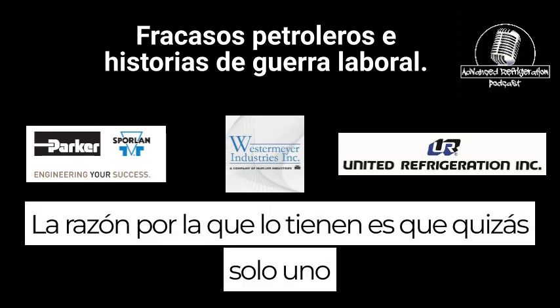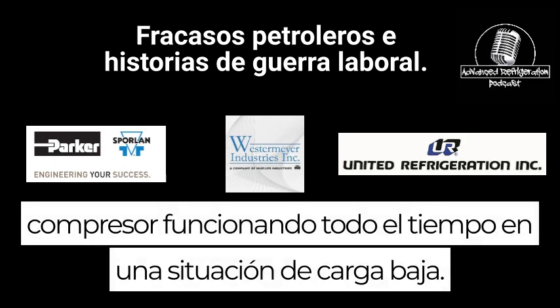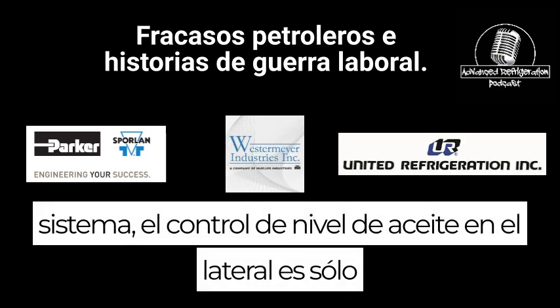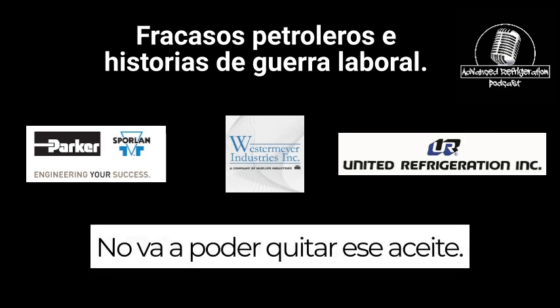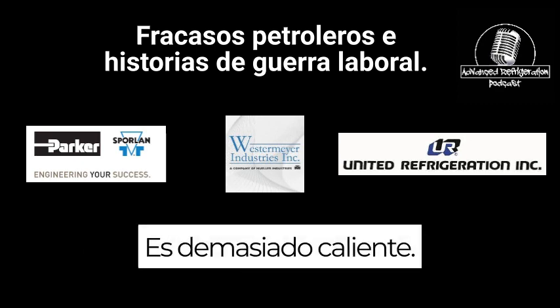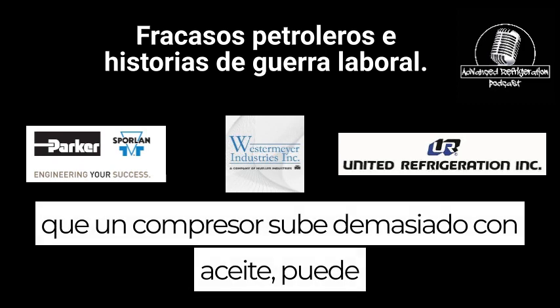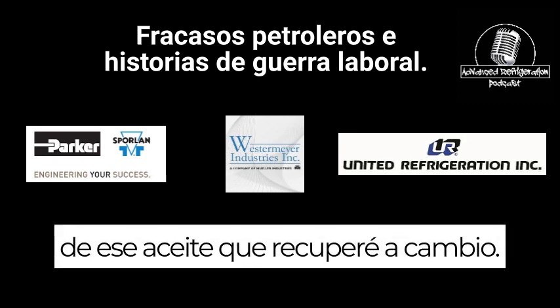The reason they have it is that you might only have one compressor running all the time under a low load situation. If you do have some oil out in the system, the oil level control on the side is only going to fill it up when it's low. It's not going to be able to remove that oil if it's too high. So the oil equalization line is there in case one compressor gets too high with oil, it can share the oil with the other compressors and expel some of that oil back to the return.